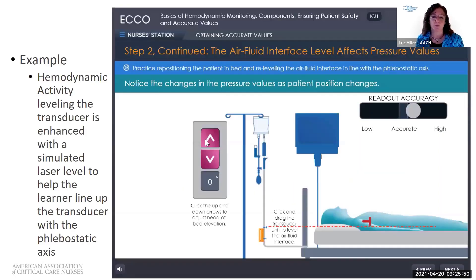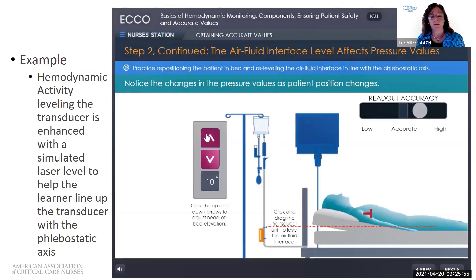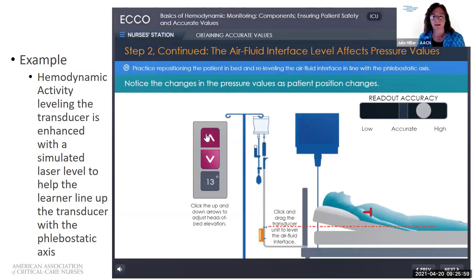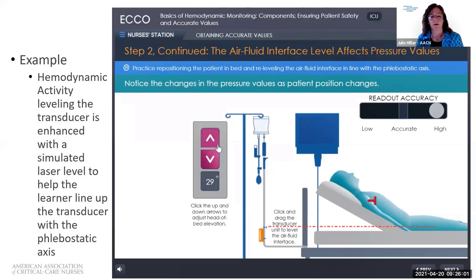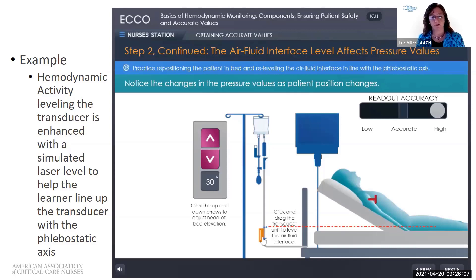This is another example of an interactive element in ECCO that provides an opportunity for simulation. It gives the nurse the opportunity to practice raising and lowering the transducer to make sure they get it to the right area. As the head of the bed goes up, the transducer is too low, and you can see the readout accuracy is incorrect, reading too high.